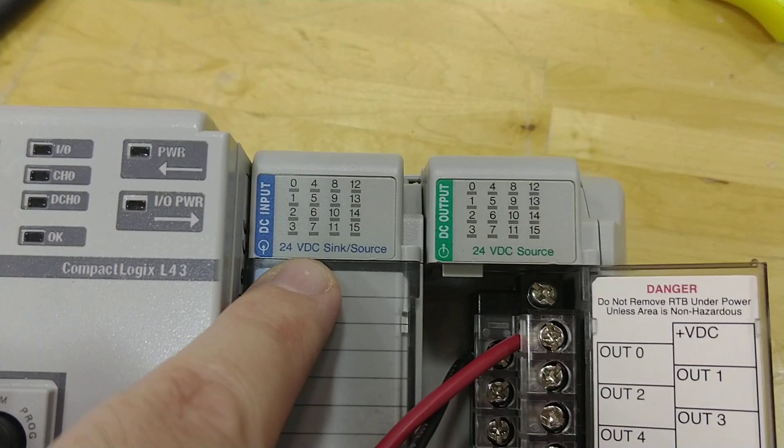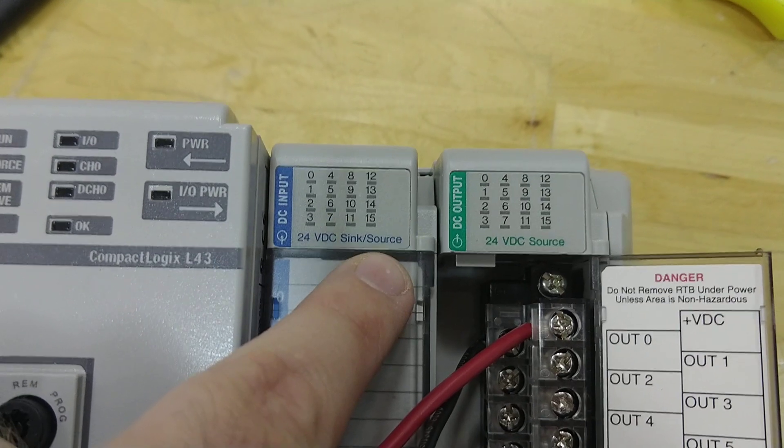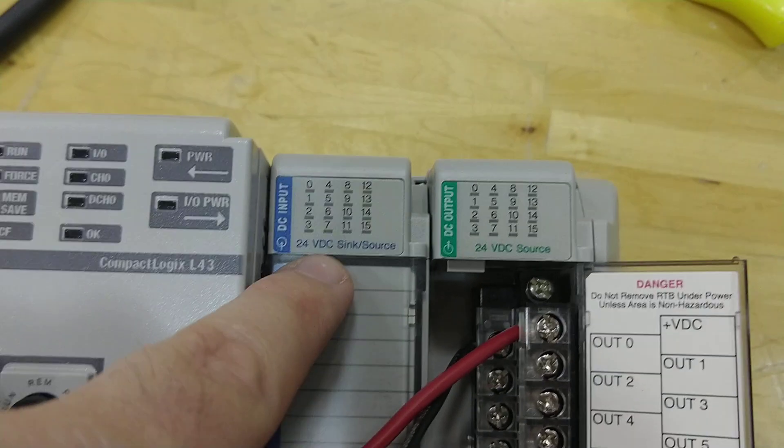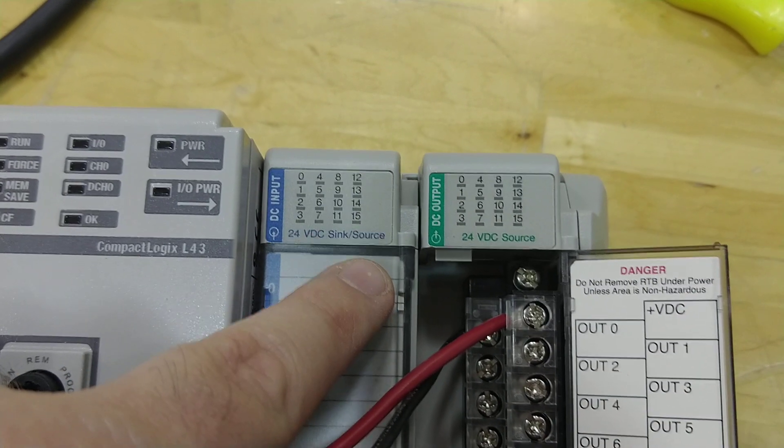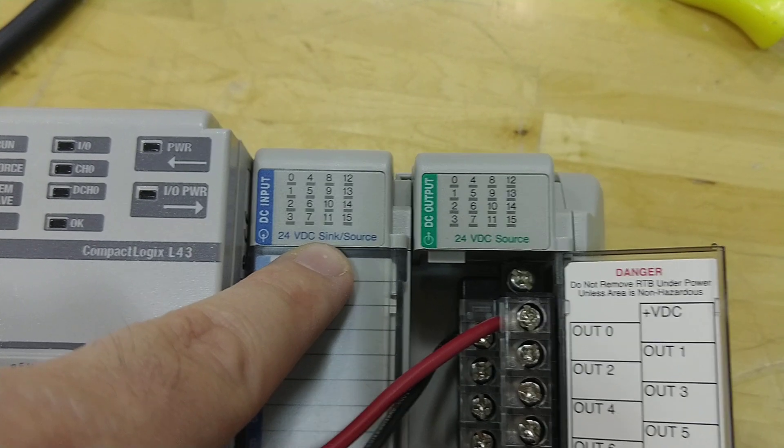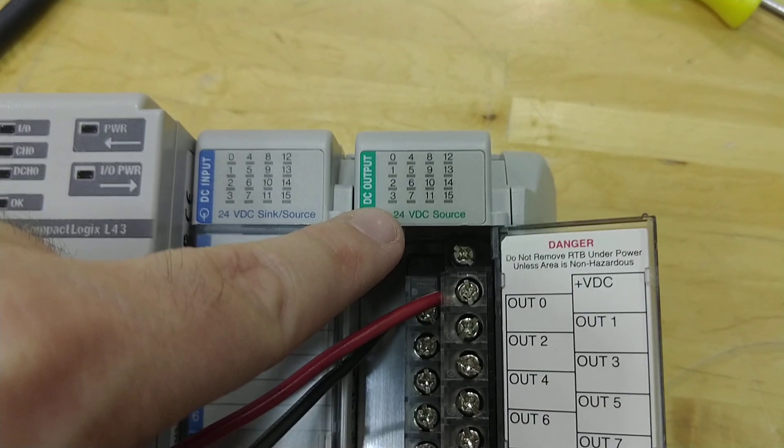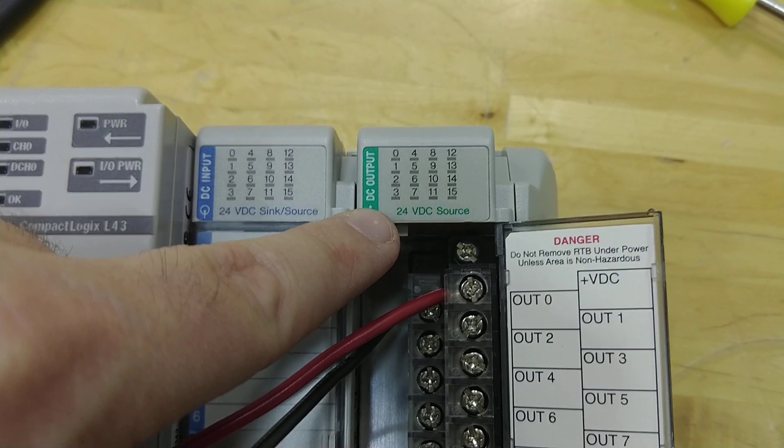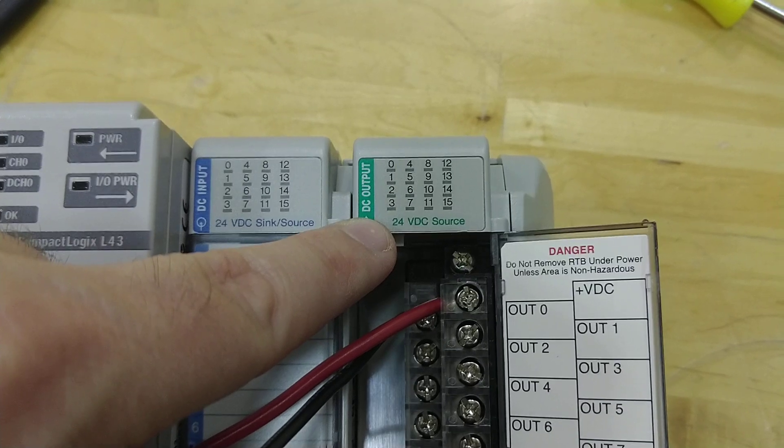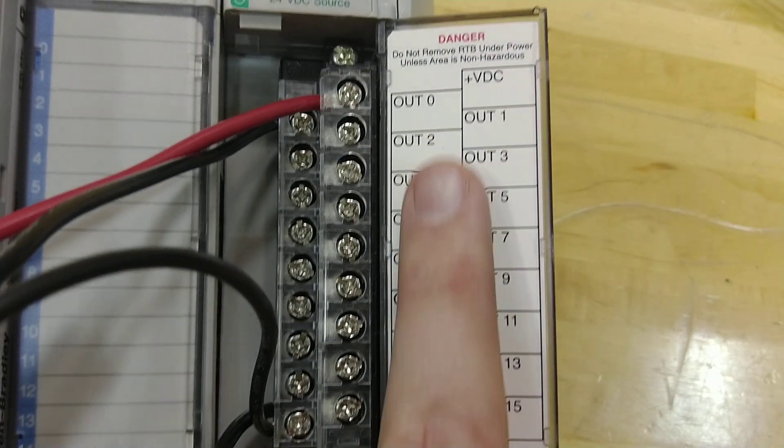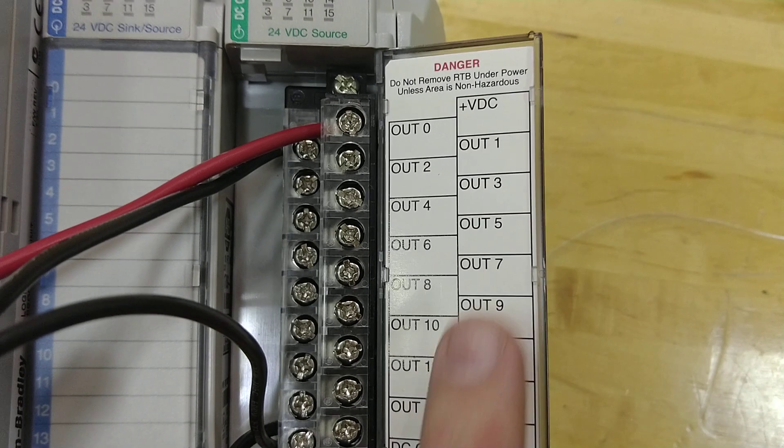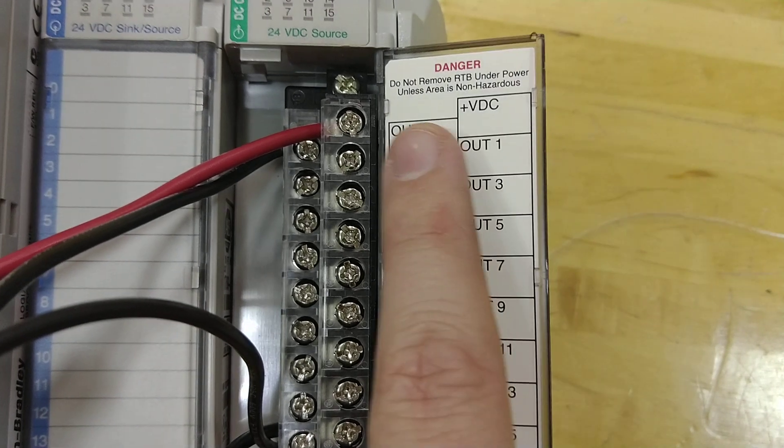If we take a look, this is 24-volt sinking or source. In theory, I could wire them either way. In this case, I wired them sinking, or wired this in a sinking format, where this is a 24-volt source only. How we wire them is all based upon right here, and you can see everything's clearly wired and attached to the terminal blocks.